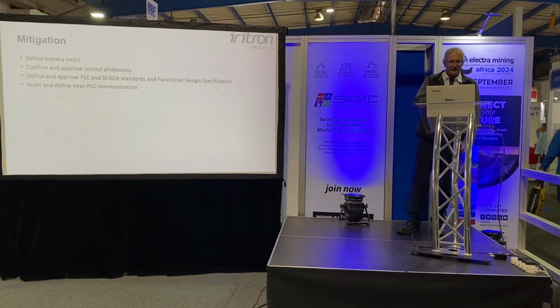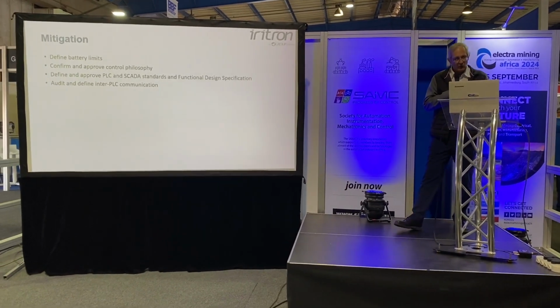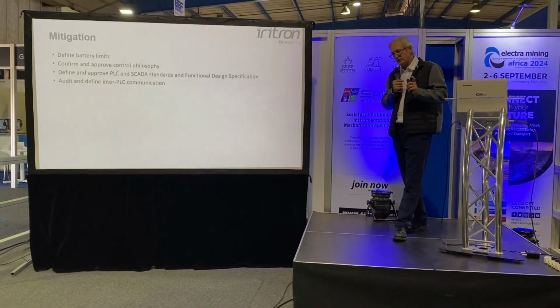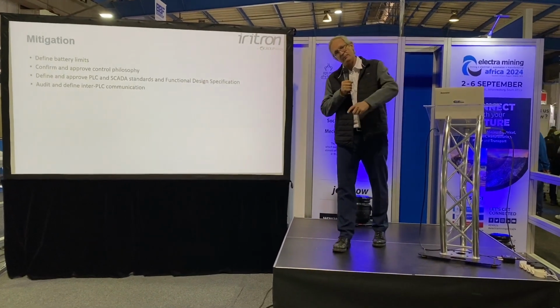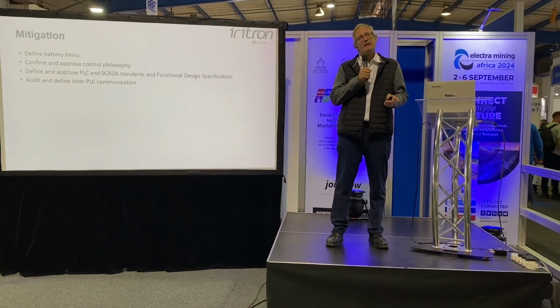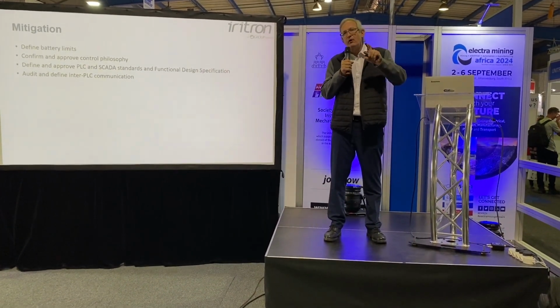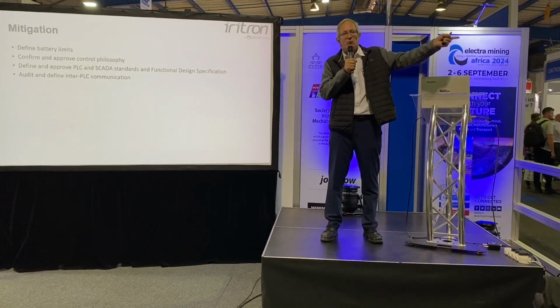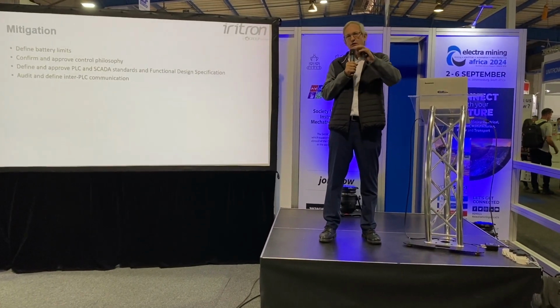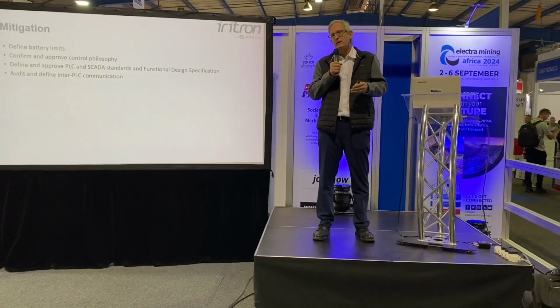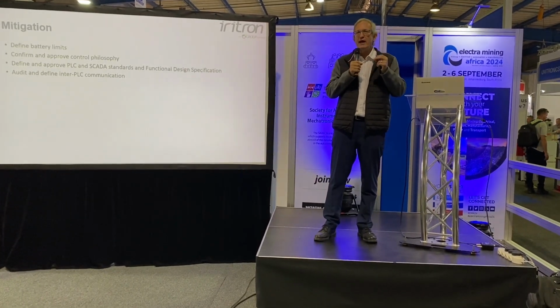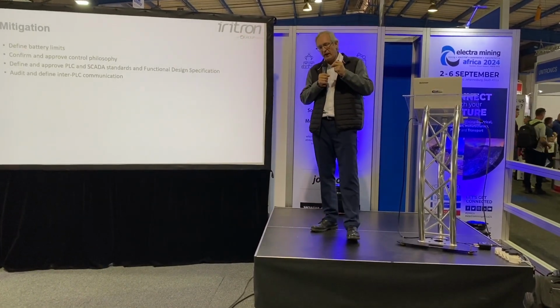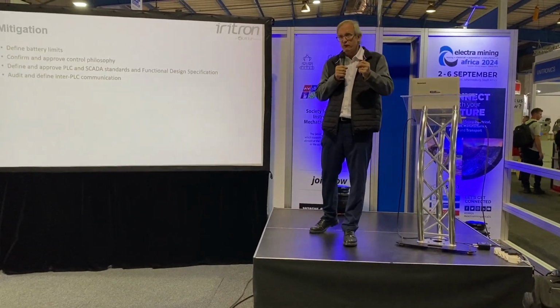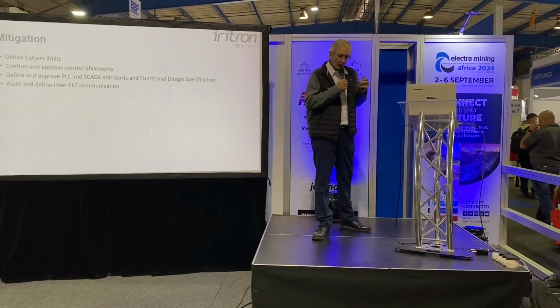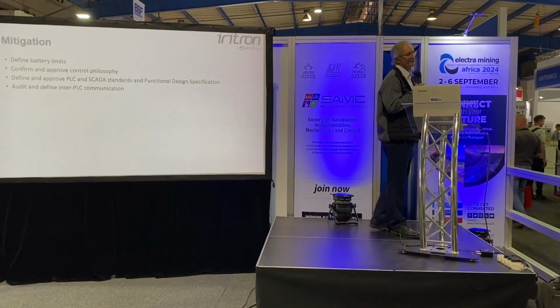Then, and this is an important one, audit and define inter-PLC communication. So go and look at the PLC and in the SCADA if there's missing parts that potentially live somewhere else. It's not that easy to do, but it is something that needs to be done. You have to actually make a conscious effort to look for those, because I can almost guarantee you will find them.